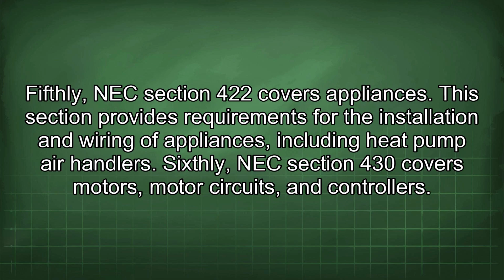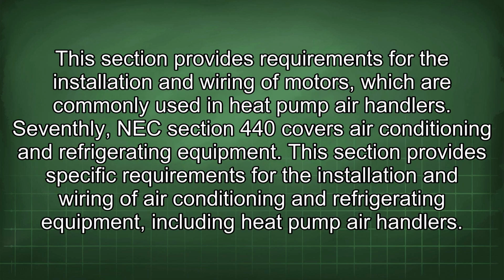Fifthly, NEC section 422 covers appliances. This section provides requirements for the installation and wiring of appliances, including heat pump air handlers. Sixthly, NEC section 430 covers motors, motor circuits, and controllers. This section provides requirements for the installation and wiring of motors, which are commonly used in heat pump air handlers.